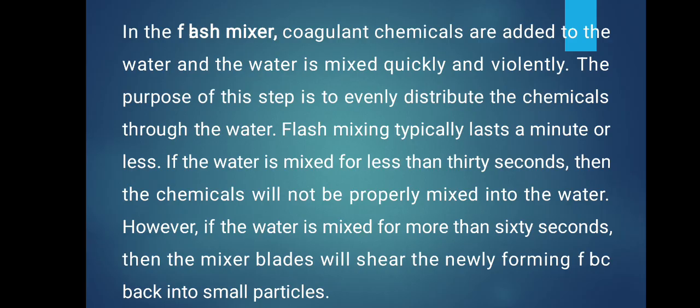The purpose is to evenly distribute the chemicals into the water. The flash mixing typically lasts a minute or less. If the water is mixed for less than 30 seconds, then the chemical will not be properly mixed into the water. If the water is mixed for more than 60 seconds, then the mixer blades will shear the newly forming floc back into small particles. Therefore, the mixing time will be within 30 seconds to 60 seconds.